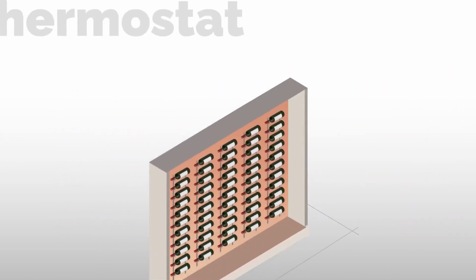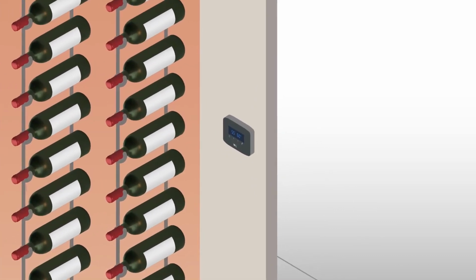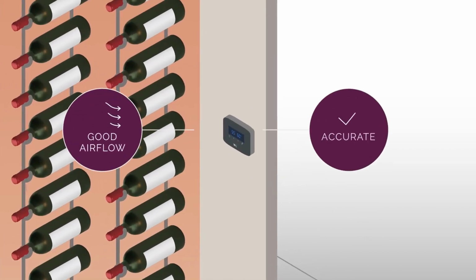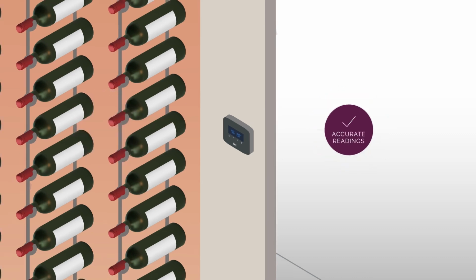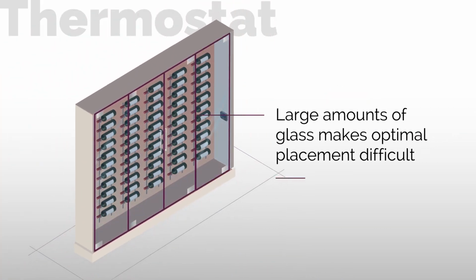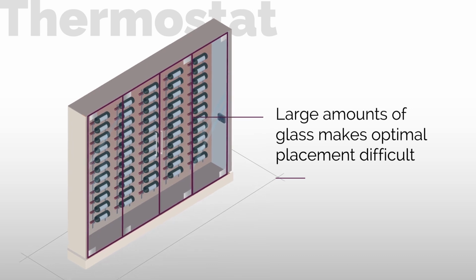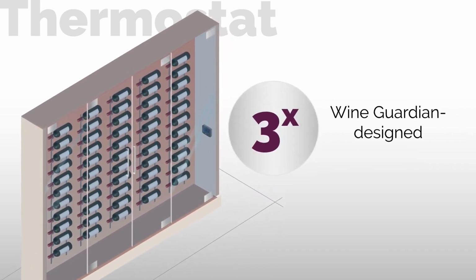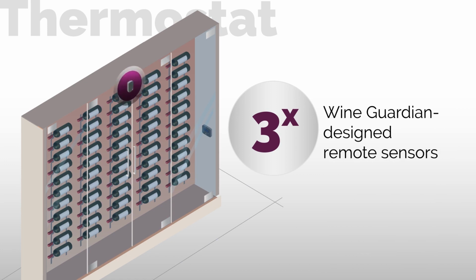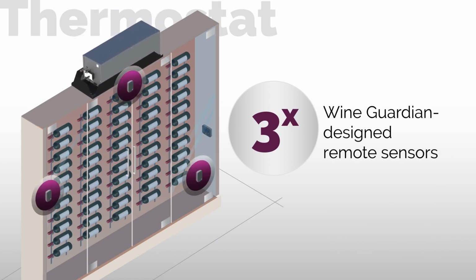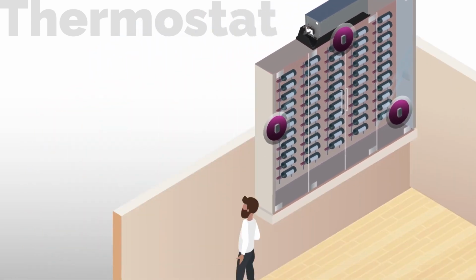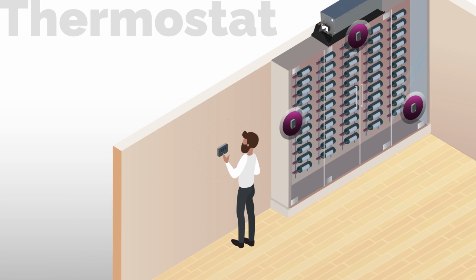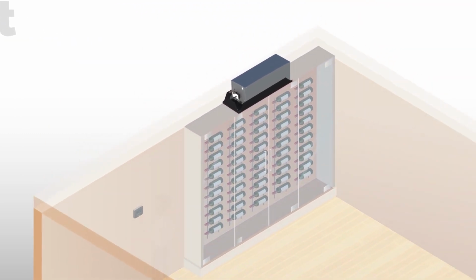The system's thermostat should be placed midpoint on a wall in an area with good airflow to ensure accurate temperature readings. Because of the large amount of glass in wine walls, placing the thermostat in an optimal location can sometimes be difficult. That's why up to 3 WineGuardian-designed remote sensors can be placed at the top, bottom, midpoint, or at the return grill of your wine wall to maximize system accuracy. When these remote sensors are used, the thermostat can even be placed outside the wine wall for convenient access.